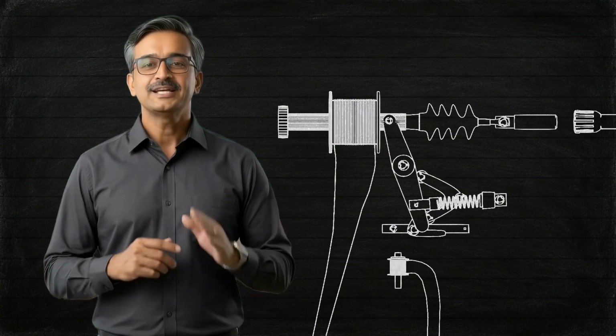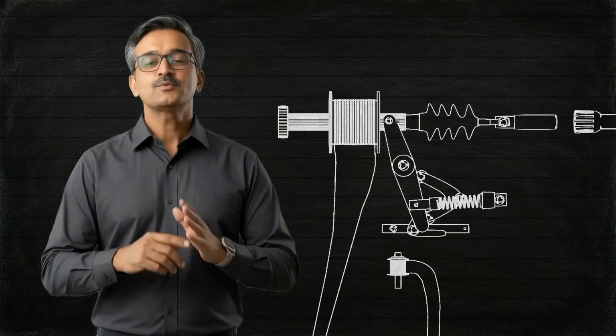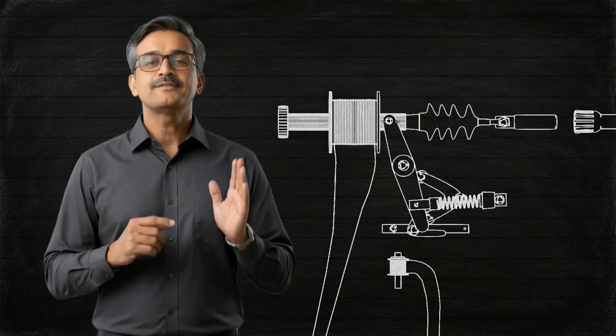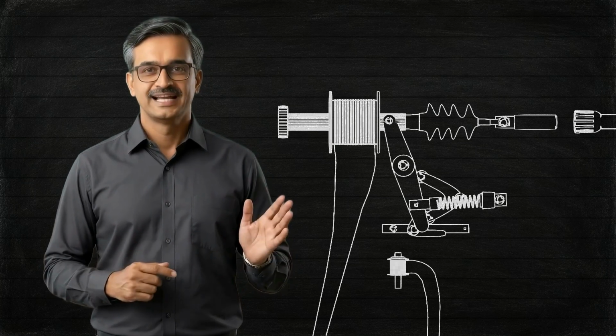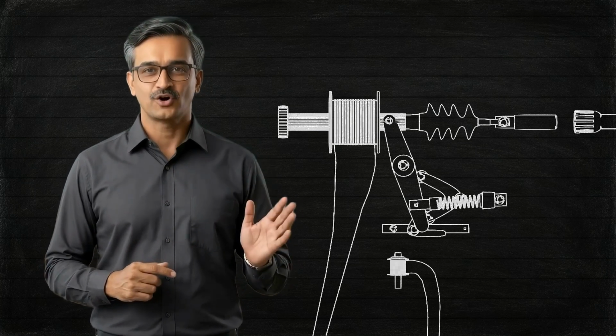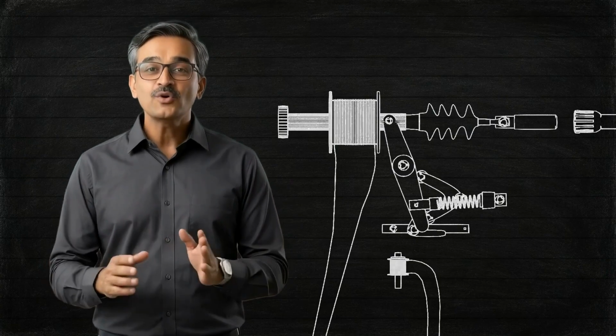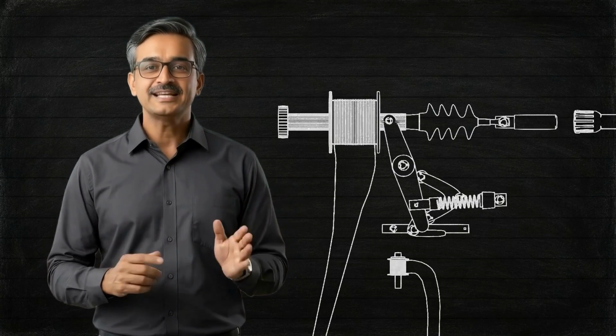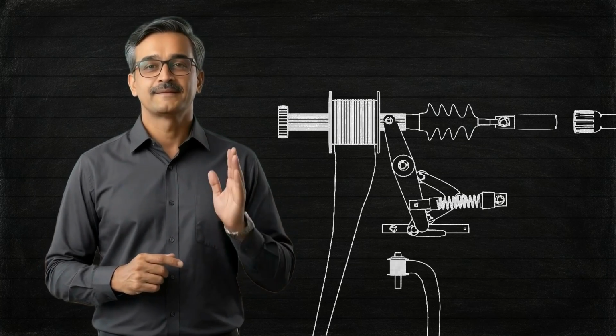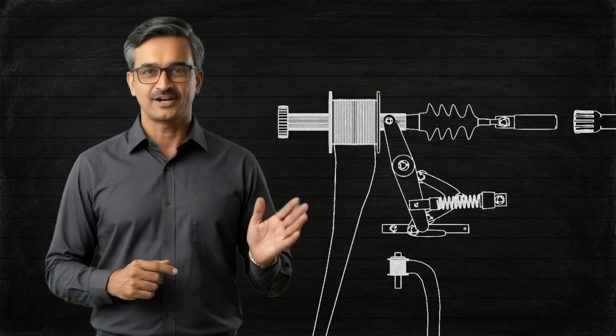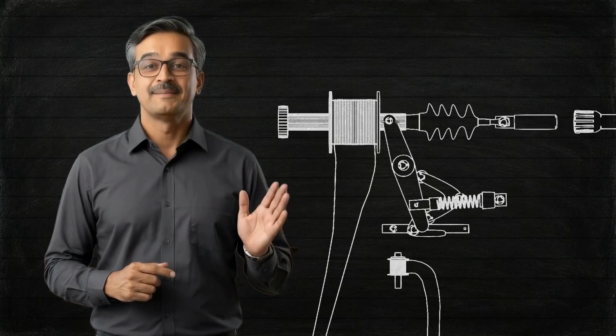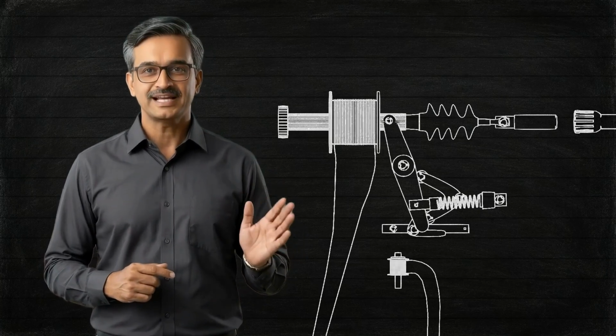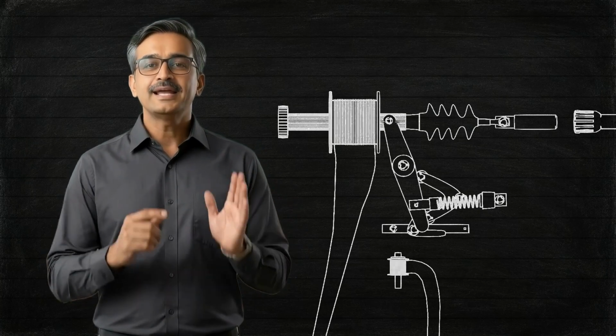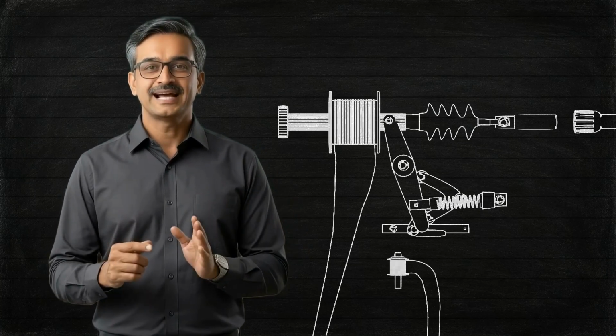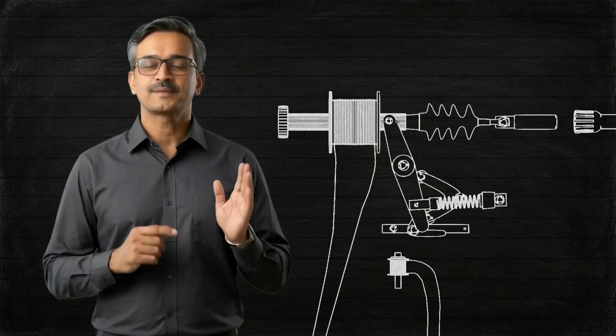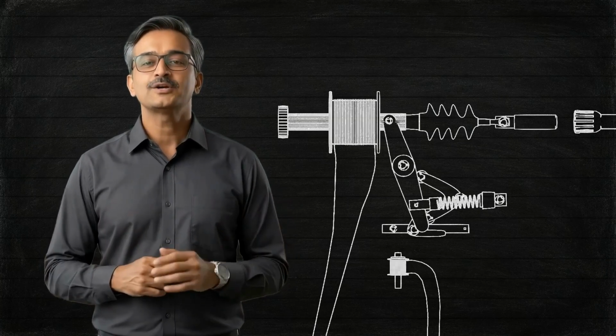This technology is still popularly used in 415-volt air circuit breakers. But for higher voltage levels, this technology has become obsolete. This is because the closing solenoid takes a large amount of power and also it takes a significant space in the circuit breaker cubicle. As this technology is backdated or obsolete, it is still used in some 11 kV bulk oil circuit breakers. However, the 11 kilovolt bulk oil circuit breaker itself has become obsolete. So, we may not have much discussion regarding this technology.